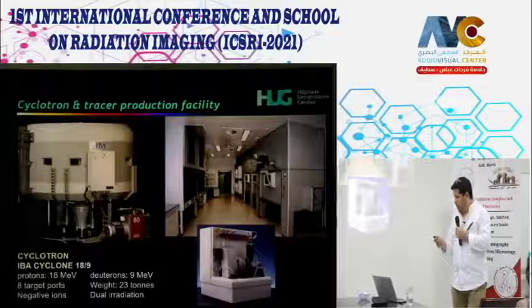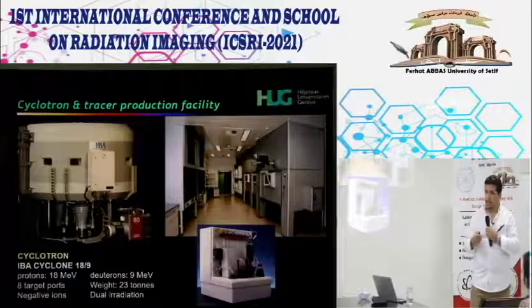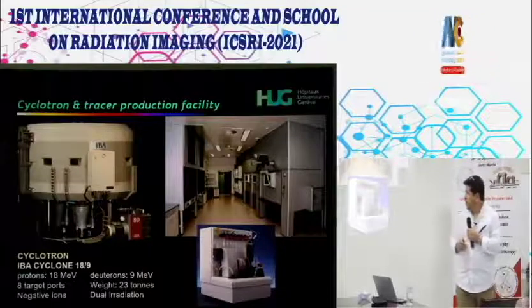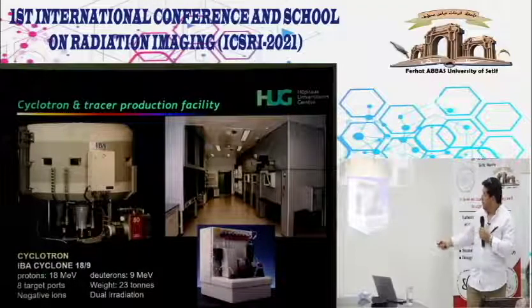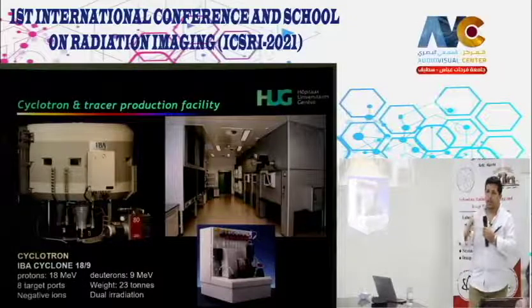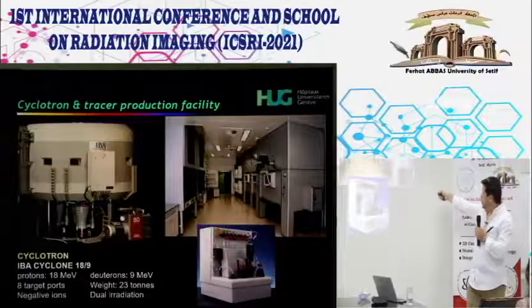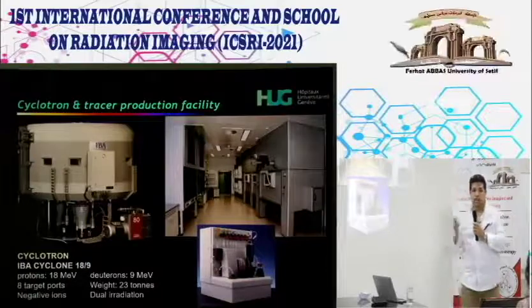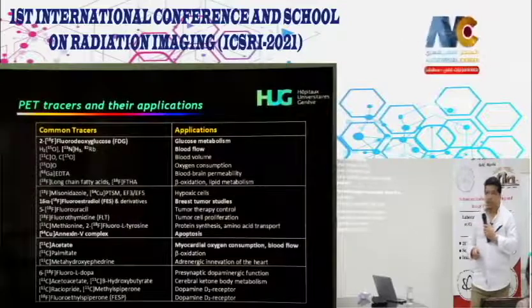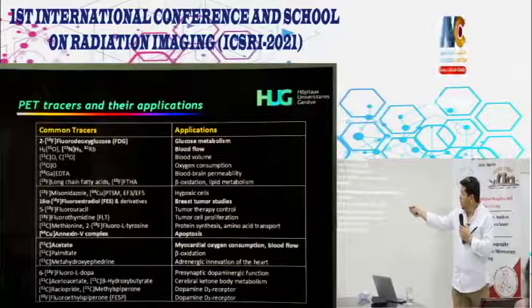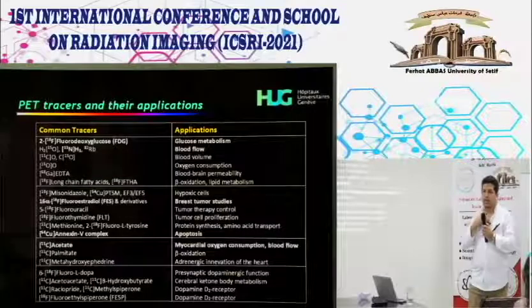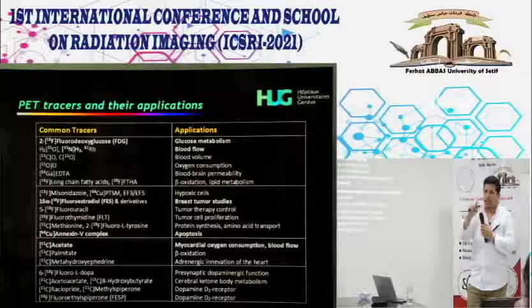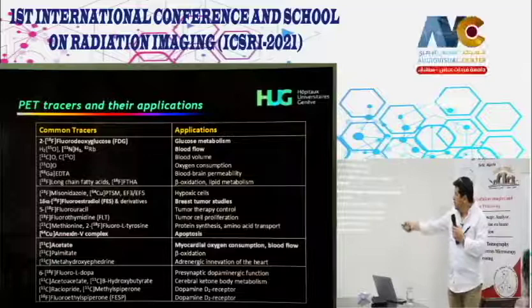Operating a PET facility requires a cyclotron for tracer production, hot cells (shielded robotic systems for handling high radioactivity), and automated synthesis modules. FDG is the most widely used tracer—for neurology, myocardial viability, and oncology, exploiting the higher metabolism of cancer cells versus normal cells. Other tracers target perfusion, hypoxia, and blood flow.